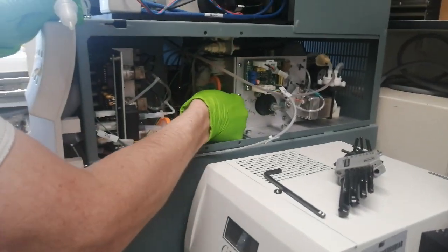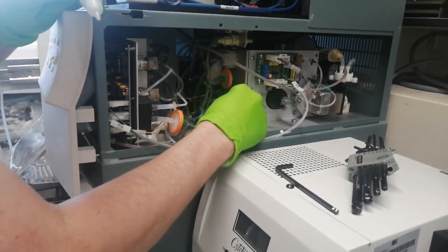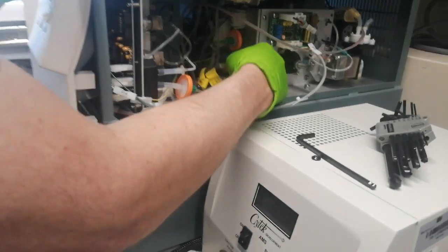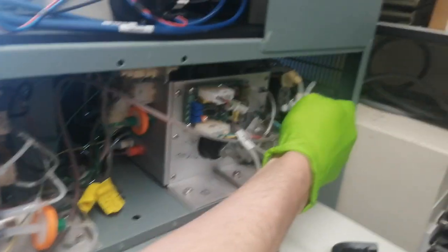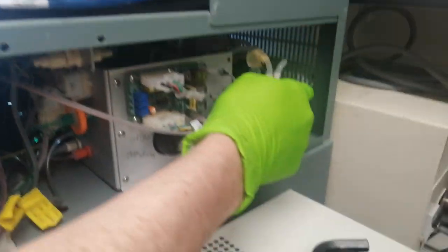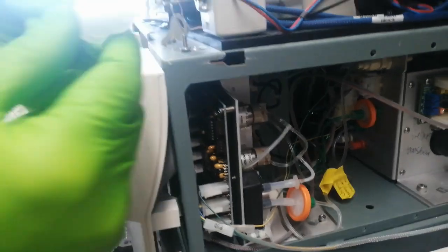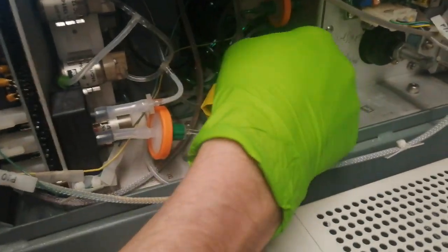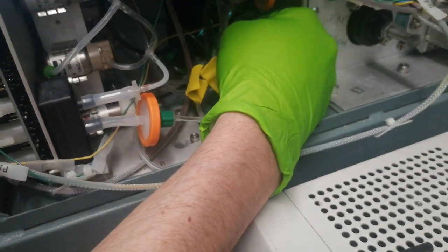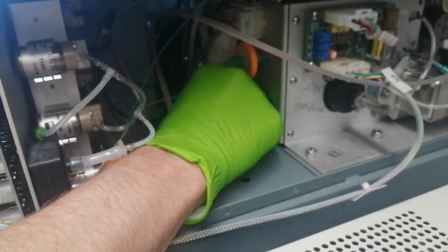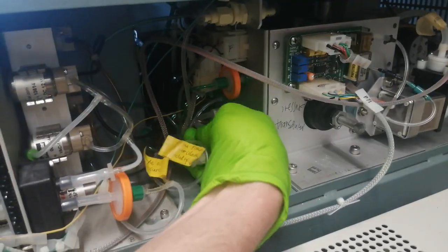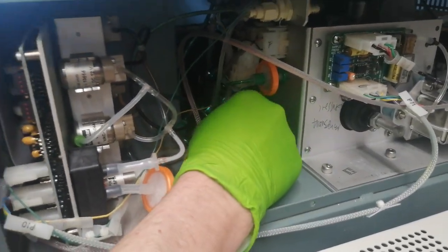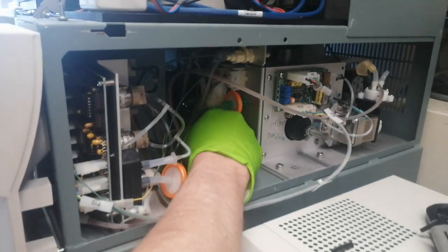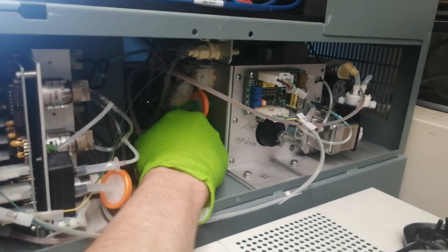Important than the others, but still gets changed. So this is the air inlet filter, so it's basically the inlet of this pump. This pump is the air pump that generates both the sheath and the sample pressure, and this is the inlet for it. I guess eventually these things will get blocked if you left them on forever, but I've never actually seen one get blocked to the stage that it starts to burn out the pump or anything.